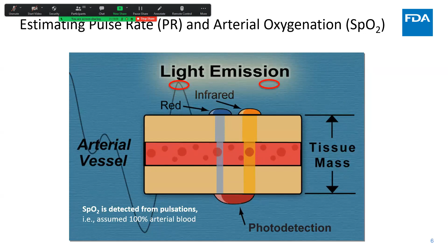Currently there are only two things required under the IEC ISO standard, and that is a display of pulse rate and a display of SpO2. And the SpO2 is assumed to be, as noted in white in the lower left-hand corner, arterial oxygenation. That said, next slide, as you're putting in all of this light and you're only getting out less than 5% of it, there are a lot of reasons why these things are challenged. And one of the reasons why myself and many others have authored clinical practice guidelines is so that people in the trenches, trying to make sense of what this value is displaying, are able to understand other things they ought to be doing to verify that this estimate of color change with hemoglobin is realistic.